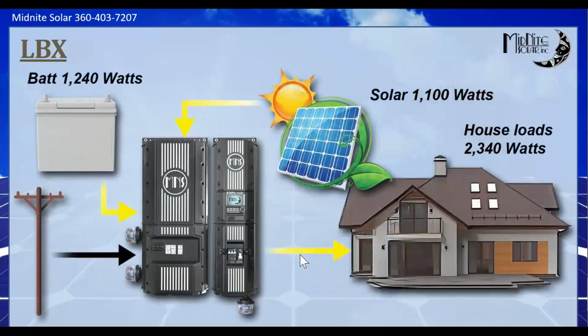So here's kind of an example of this. You can see here when it's in LBX mode, all the loads are coming from the solar and the battery combined. So if there's no solar, it all comes from the battery. If there's enough solar, like say in this case, say it was 5,000 watts of solar, then we would send 2340 to the house and we'd send the other 2660, if I got my math right, to the battery to charge the battery. So you can actually charge or discharge the battery in that mode, from the solar. But the point is we actually open the relay and we're ignoring the grid at this point. Something I do want to point out in this mode is that LBX is an absolute, just like time transfer is.